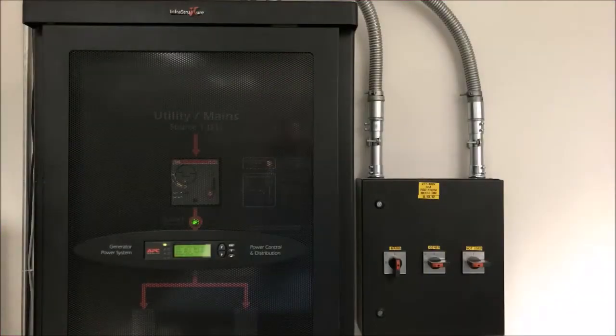The ATS can give generator service reminders based on time and run hours. The default interval for these reminders is once yearly and 300 run hours. The following steps should be performed when the generator is serviced. It can also be used to clear active service level alarms.